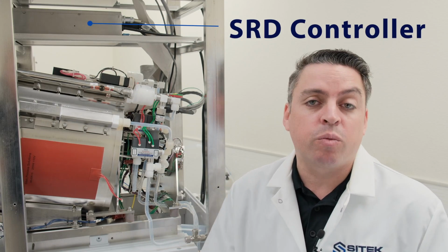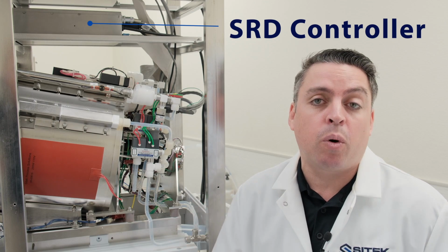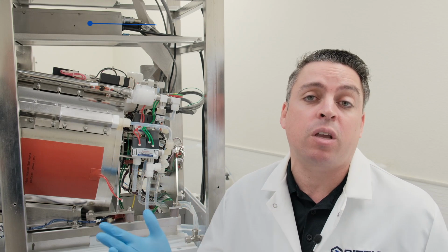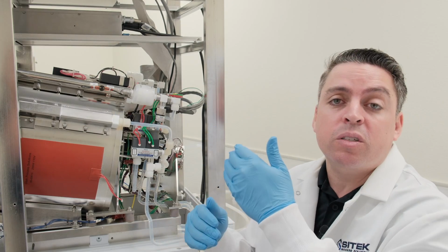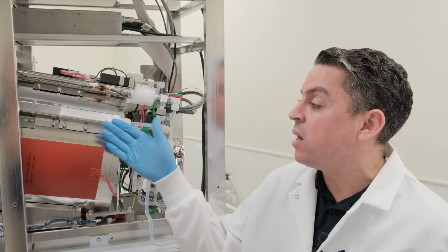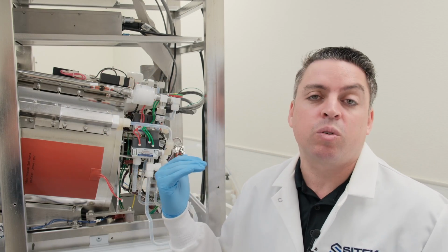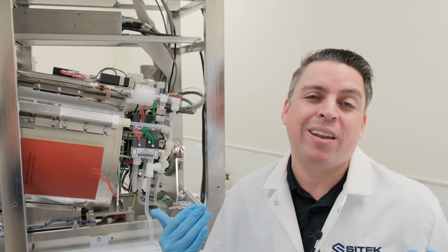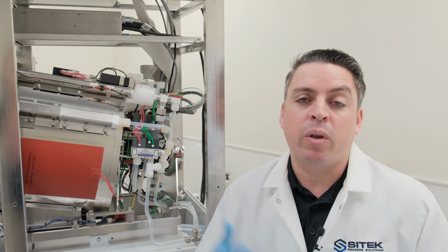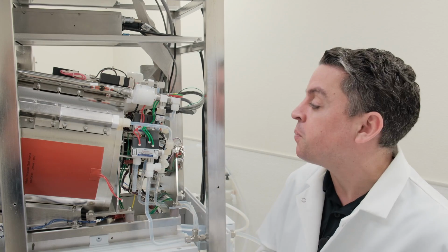The second common cause would be a problem with the controller. Usually that could be a failed relay, but it can also be damage to the board, the traces, or anything else, especially on older systems. And if that's the case, what you want to do is swap controllers and see if the problem stays with your head assembly or if it follows your controller to another chamber. Obviously, if it follows your controller, then what you can do is send that into SITEK for a repair, and we have a turnaround of normally a couple weeks on that.